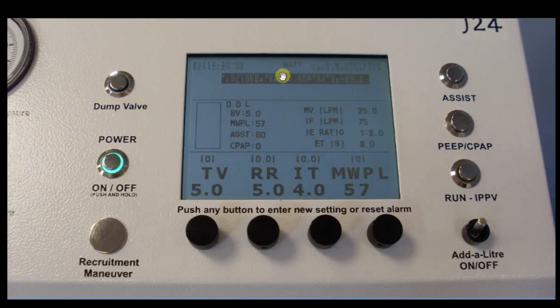If this was a live video rather than a picture, you'd see that BAT would be flashing. It flashes there to alert you to the fact that it's not running on mains and that you're running on battery power. To the left, the battery's actual voltages are shown here. Battery 1 is 12.3 volts and battery 2 is 12.2, and they're both shown as OK. As these values decrease, this is constantly updated.